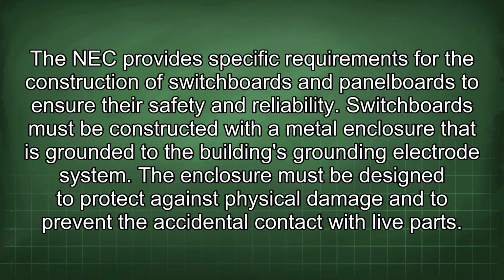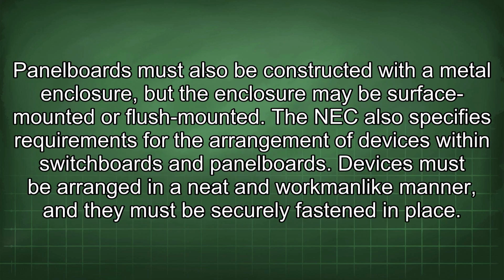The NEC provides specific requirements for the construction of switchboards and panel boards to ensure their safety and reliability. Switchboards must be constructed with a metal enclosure that is grounded to the building's grounding electrode system. The enclosure must be designed to protect against physical damage and to prevent accidental contact with live parts. Panel boards must also be constructed with a metal enclosure, but the enclosure may be surface-mounted or flush-mounted. The NEC also specifies requirements for the arrangement of devices within switchboards and panel boards. Devices must be arranged in a neat and workmanlike manner, and they must be securely fastened in place.